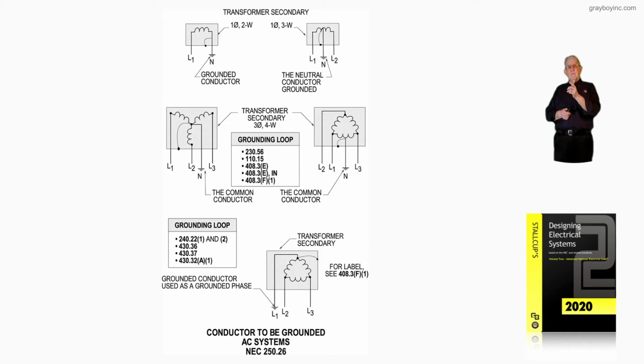Now notice to the right, you have that closed delta. You have three windings. Notice there are two 240-volt windings each. You have three 240-volt windings. You've tapped one of them in the center. It's a common tap point. And you get 120-volt from L2 and L3 to the neutral. But from any L1, L3, and L2, you get 240-volt.